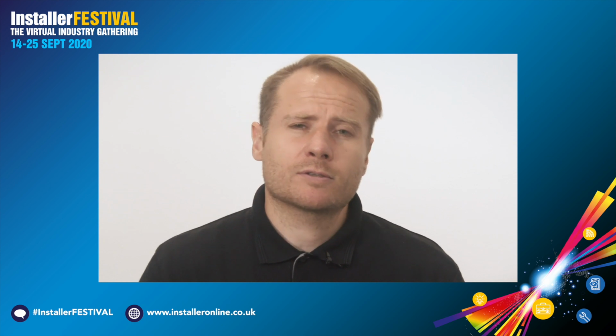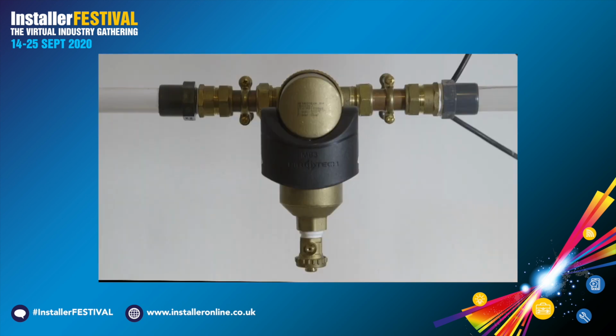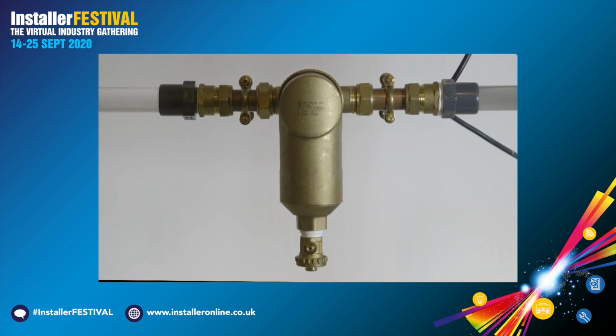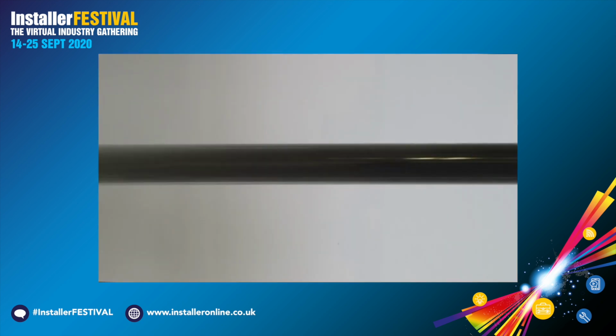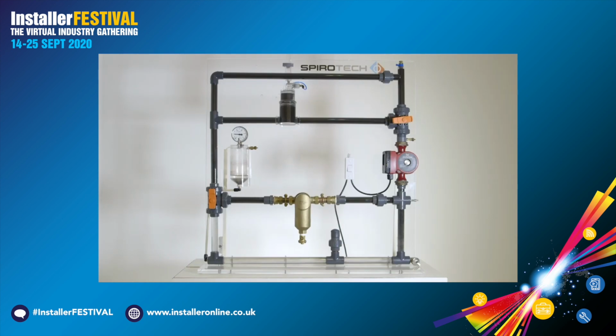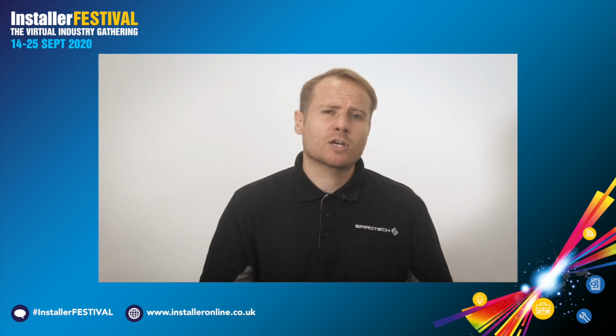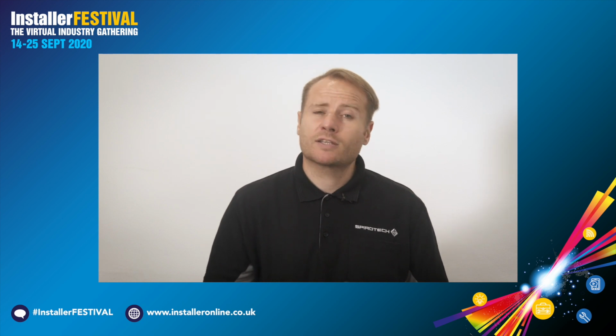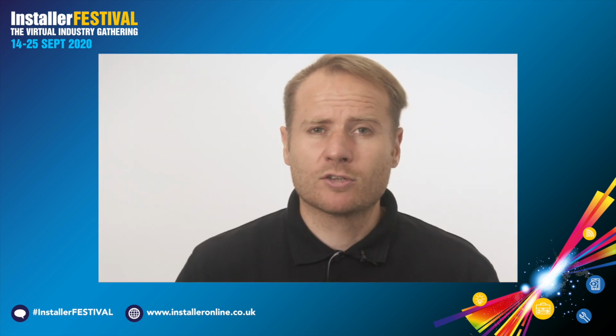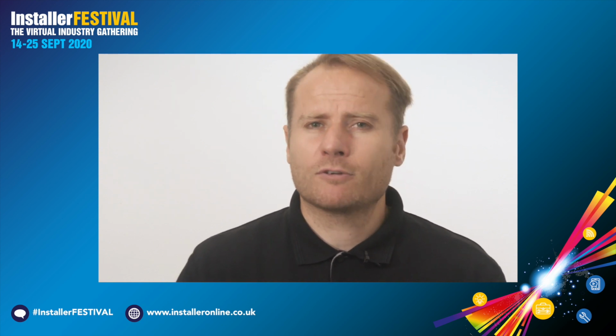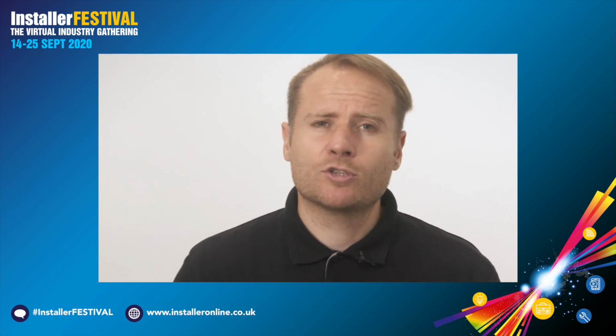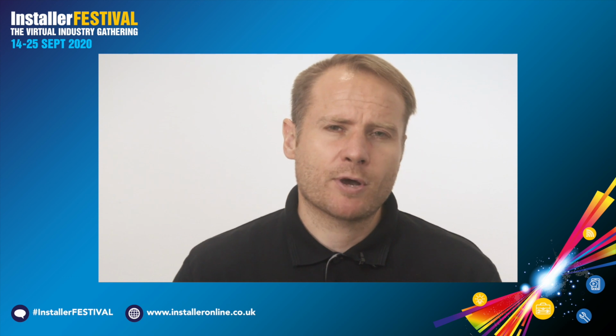I would now like to introduce some dirt so I can explain to you exactly how the separation technique works. So we take a nominal bore, say 22 mm pipework, we expand the area. By opening up the area, we reduce the speed or the velocity of the water as it enters the separation chamber. It's in this chamber, or dirt chamber or separation chamber, where we reduce the velocity, that the SpiroTube performs its functions. The first function is to literally separate the dirt particles or the microbubbles from system flow. The second function is to counteract or reduce the turbulence. The less turbulence, the better the separation.